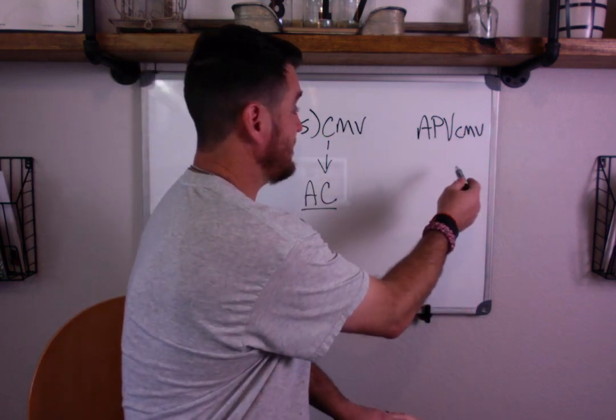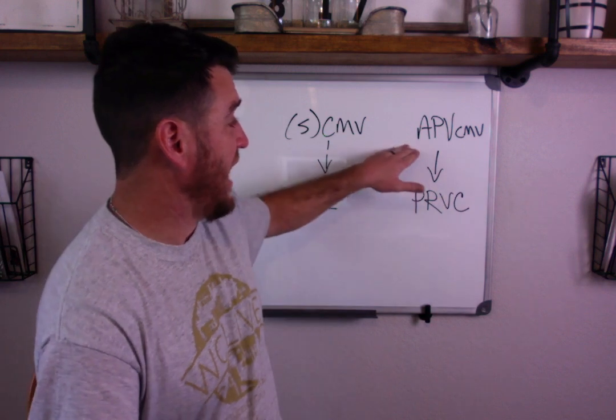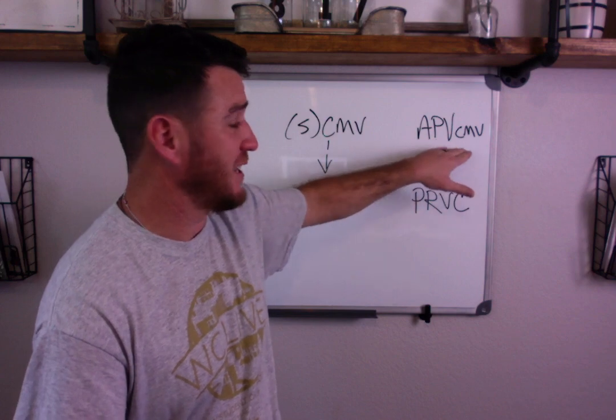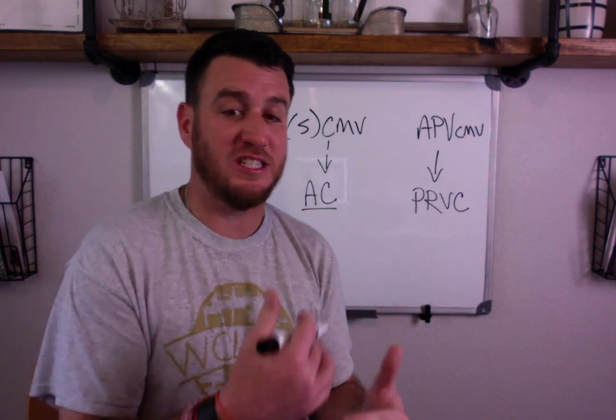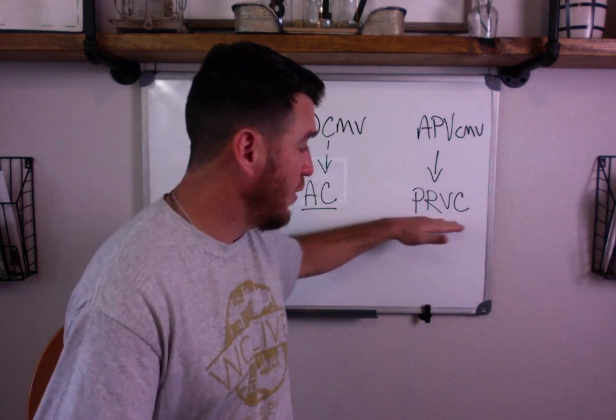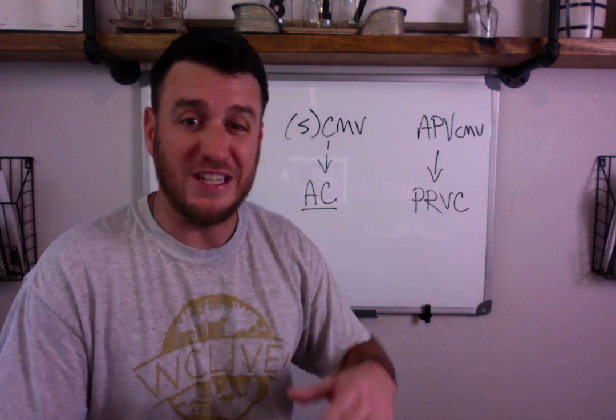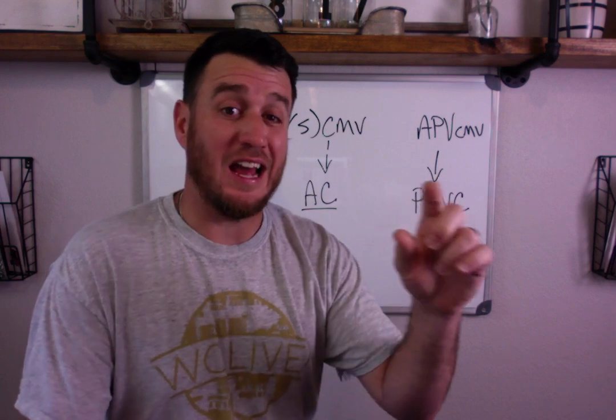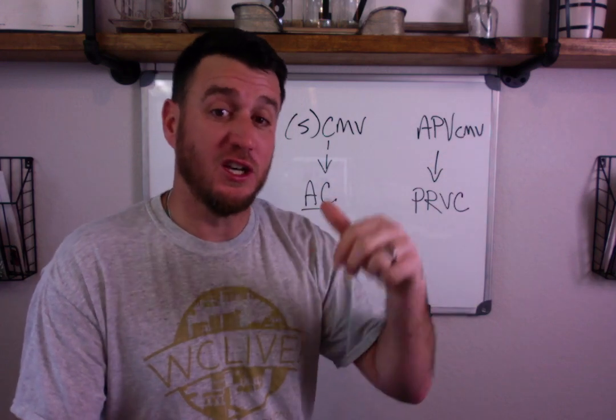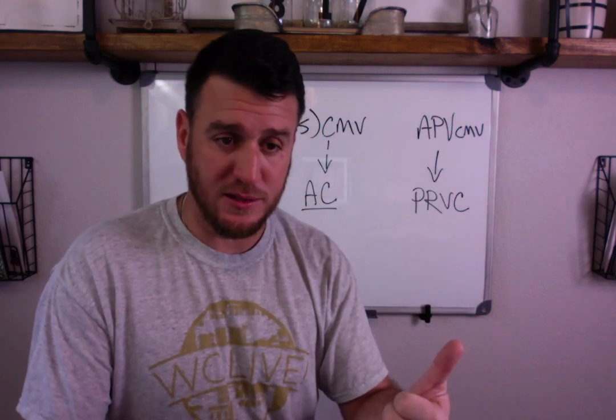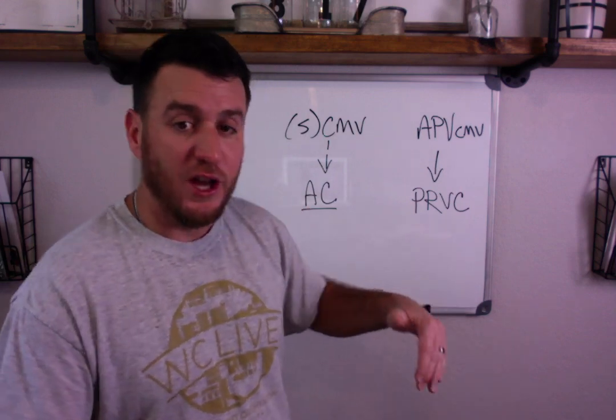APV-CMV is the same as PRVC — Adaptive Pressure Ventilation. The reason they call it adaptive pressure ventilation is because the pressure adapts to the feedback it receives from the patient, just like PRVC. Remember, in PRVC — pressure regulated volume control — we set a target tidal volume, we set an inspiratory time, and we use the high pressure alarm limit as our maximum delivery pressure. The vent gives a test breath, assesses plateau pressure and static compliance, then the next breath delivers a pressure to achieve the target tidal volume.